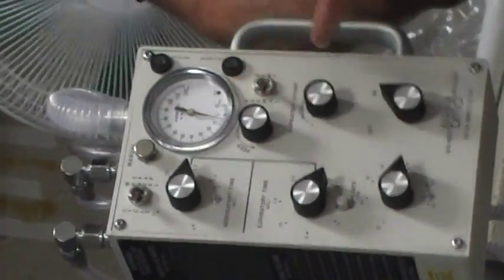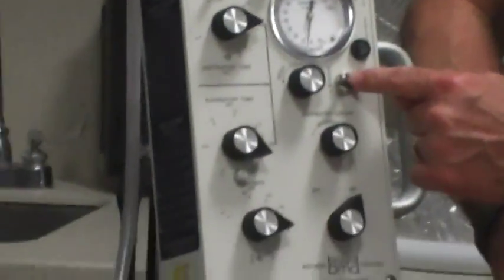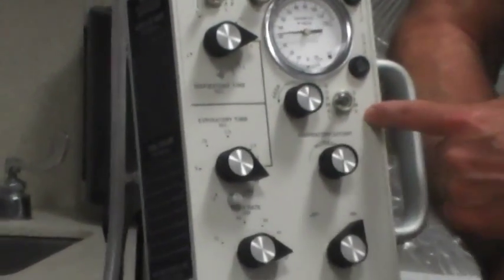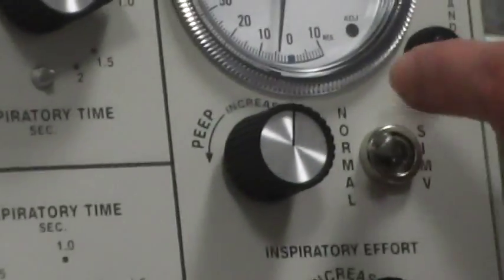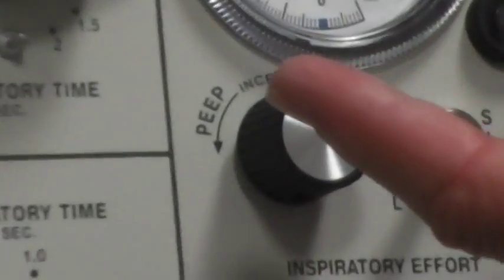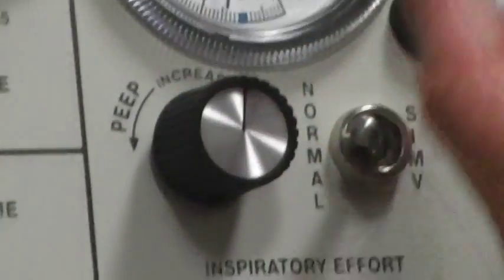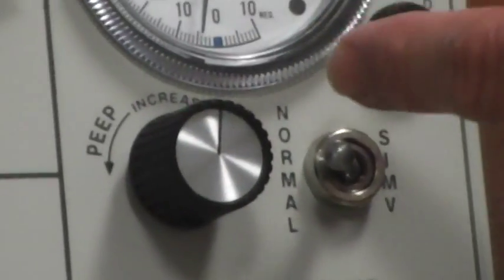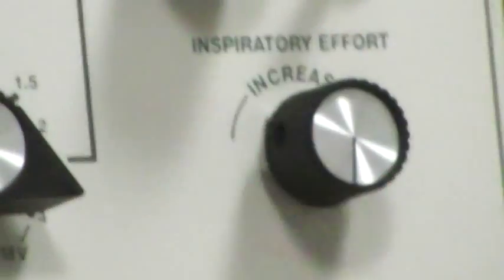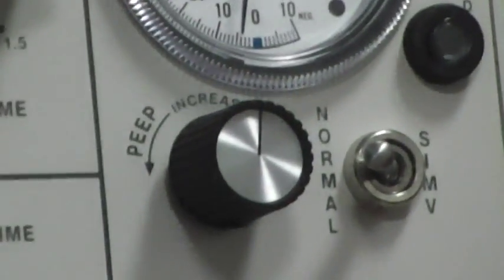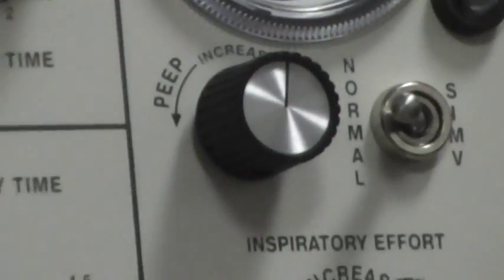So we set our PEEP. Now, there's a lever here that says normal or SIMV. Normal is actually assist control. I'm going to set my sensitivity next, but I set my rate at 12, so if the patient's not breathing at all, they're going to get a rate of 12. If the patient wanted to breathe at a rate of 20, as soon as I set my sensitivity, they're going to get whatever rate they choose. I'll go over SIMV in a minute.